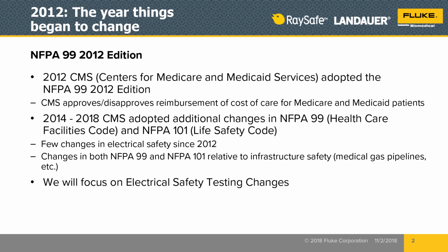So NFPA 99 had a lot of changes come through in the year 2012. So their 2012 edition had a number of changes. In 2012, not only did the standard change significantly, but since that point, the Centers for Medicare and Medicaid Services, CMS, implemented a mandate saying that Medicare and Medicaid reimbursement was tied to compliance with NFPA 99, specifically to the 2012 or newer editions, to try and encourage some conformity and compliance to the changes that were happening.